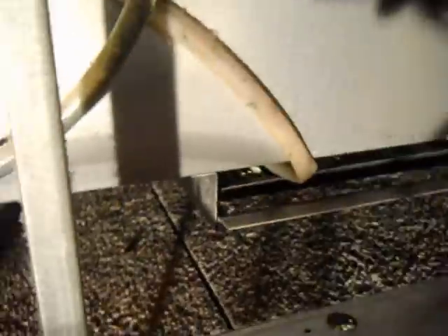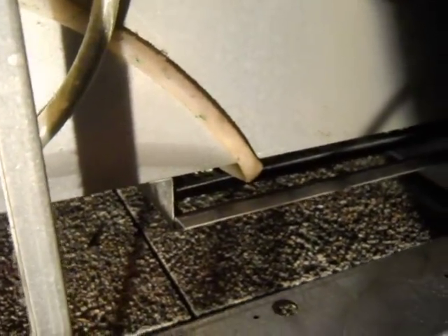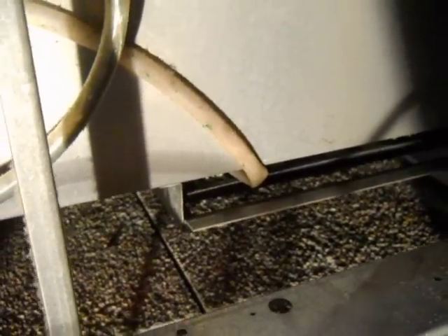And then it just is kinked right into the drain pan. Just look at this kink. And this is how the factory does this. It's a joke. This is just disgusting. Engineers should be taken out, tarred, and feathered. Man, I'm gonna talk to these Beverage Air guys and give them a piece of my mind. This is just a joke.